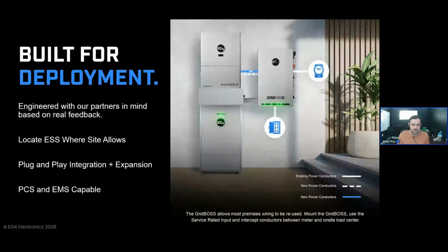We talked a lot about the GridBOSS and what it does there to kind of enable a bunch of different sources to be pulled to that single location and make for very easy design by giving you dedicated inputs for each one of those different components. But even going a step beyond that, what we've enabled with this device is to enable you to locate the different components of the system on site where the site allows. You're not having to significantly rework the site in order to fit an energy storage system into a space that the energy storage system kind of dictates based on the way that it's designed.